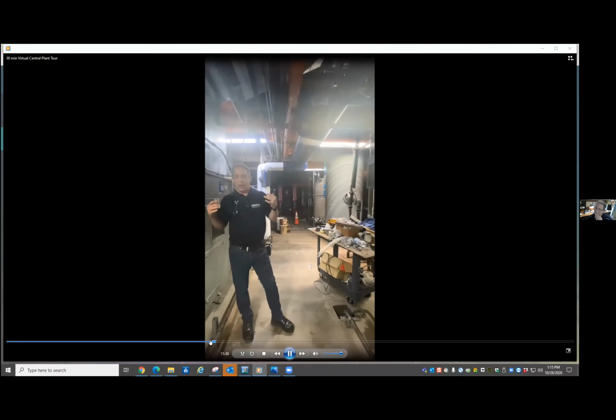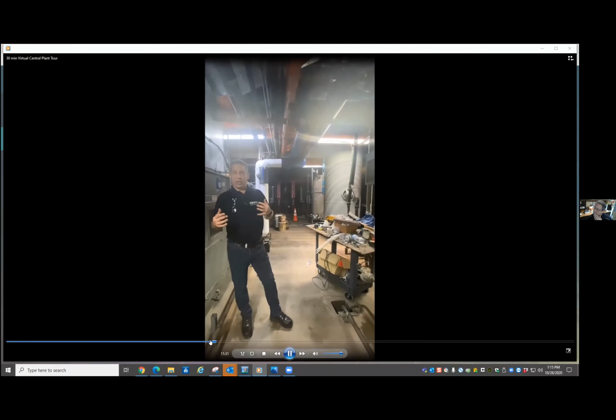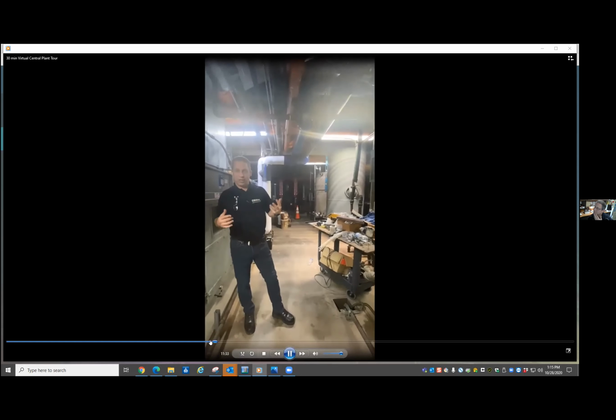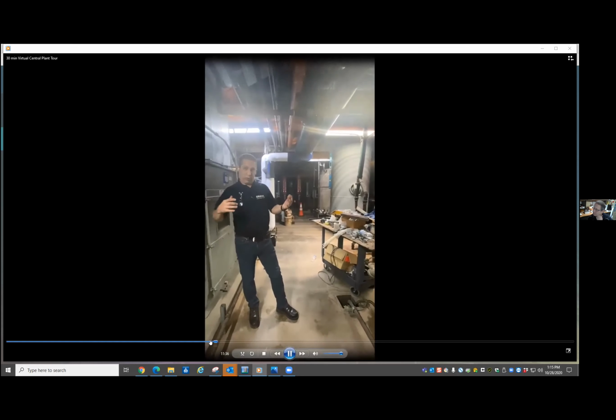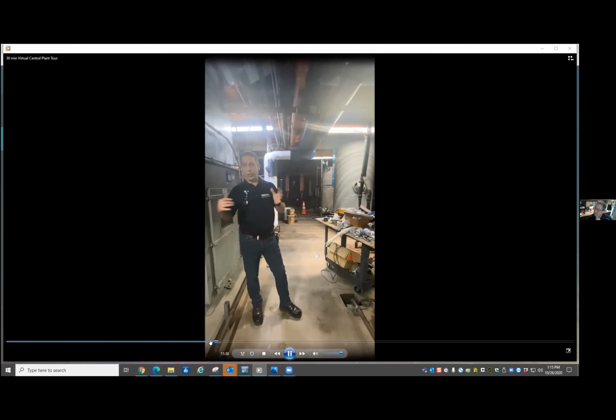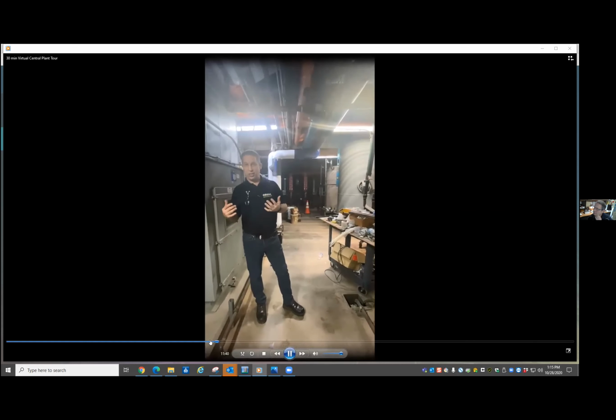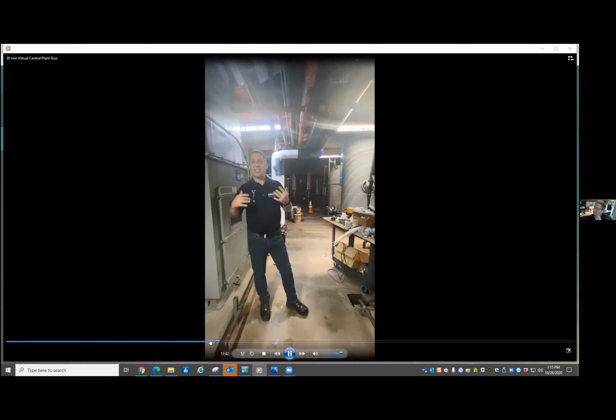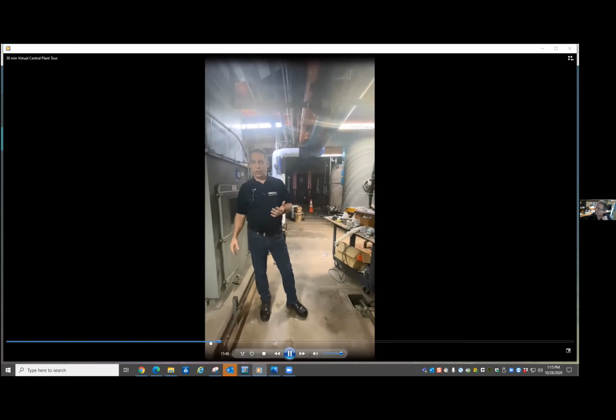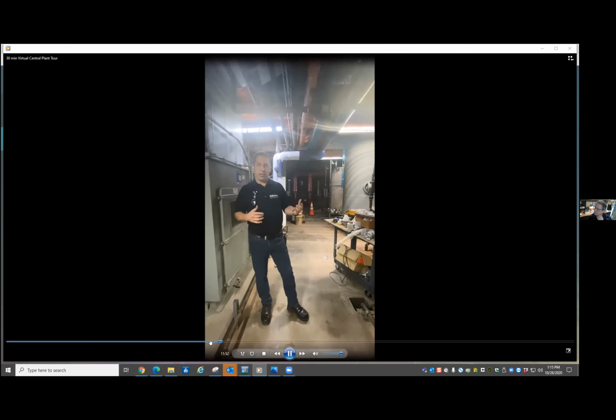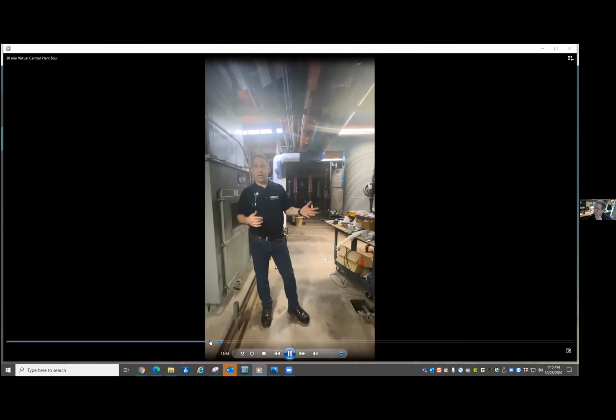If you think about in the early morning, your car has dew on it - that's condensate. When we take that cold water and run it through the air handlers, we create a lot of condensate, in excess of approximately 1 million gallons a year. Normally, the condensate just runs right down the drain. So we're in the middle of a project where we're going to collect all of that condensate and pump it back to the cooling tower, where we use 20,000 gallons a day.